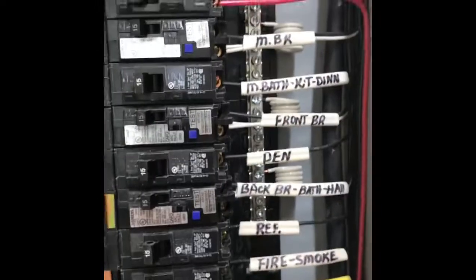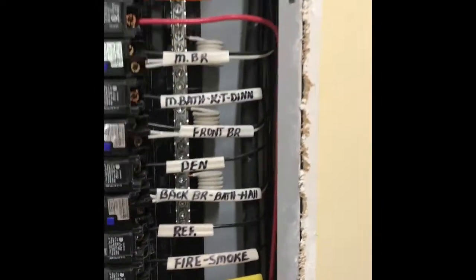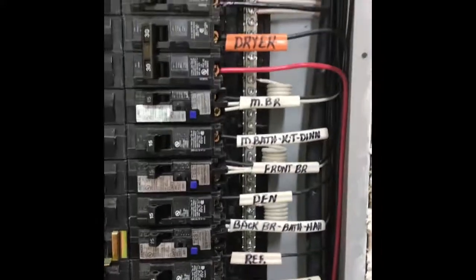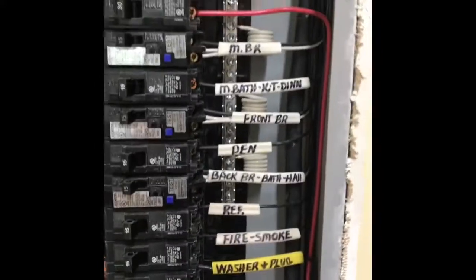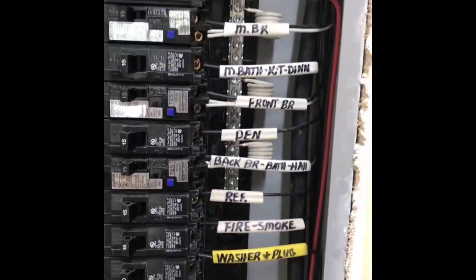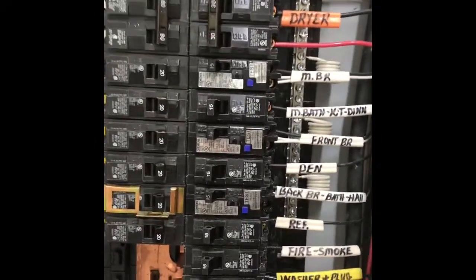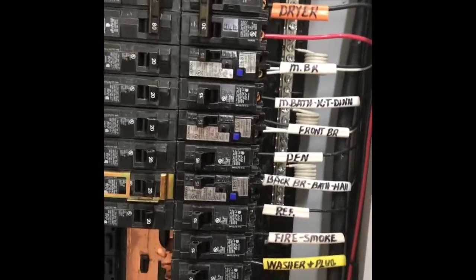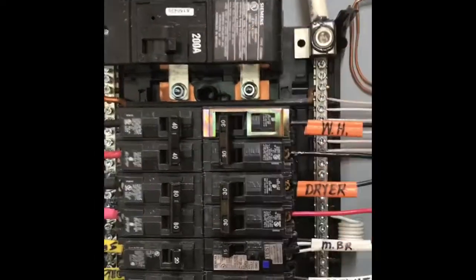That's called the dead front cover. That's because the bus bar and everything in here doesn't have any overcurrent protection, so if it shocked you, it'd probably kill you, or it would continue to shock you until the transformer blew or something like that, because all these breakers protect the line circuits, not the panel. Maybe the 200, you'd be lucky enough it trips, but just don't touch anything here if you don't know what you're doing. Anyways, this is actually a great panel, so I wanted to go over what right looks like. This panel does have a 200 amp main, but actually this panel is a sub panel.